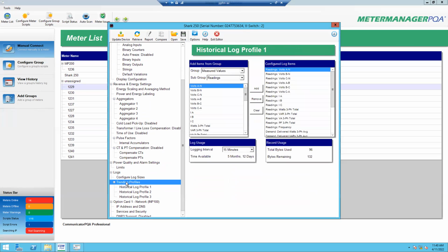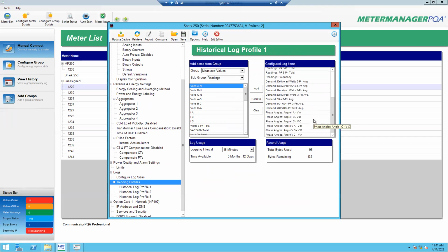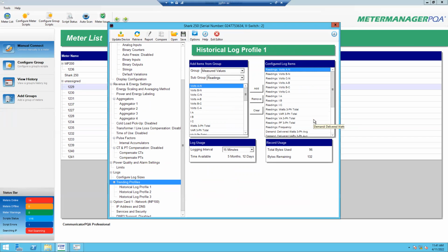So the way they do it is, depending on the meter, you have different logs that you can log data into. One of the reasons you might want to pick different logs is you may have one log that logs every 15 minutes, another log that logs every minute, or just to group different things together. Maybe energy in one log and volts and amps in another log, which is some of what they have here.